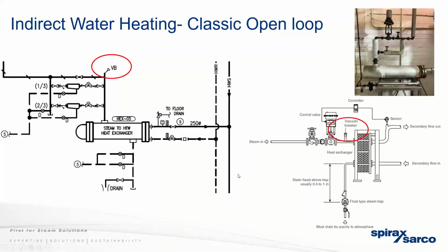But you'll see on both these types of systems, you have a vacuum breaker. With modulating control, it'll change the pressure available within the heat exchanger, and thus to the trap. So you could end up in a vacuum, and a vacuum breaker's purpose is to open up and set the system after the control valve to atmosphere. How it does it is it opens up and air will fill the space. Once you have air filling the space, it'll allow the trap to gravity drain if it's sized properly for the static head from the heat exchanger out to the trap. So this allows air in, brings it to atmosphere, and the static head will be enough force to push the condensate through the trap.